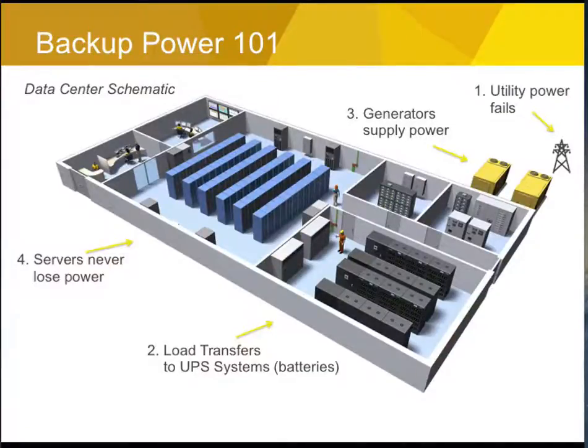Those power systems and batteries are designed to run for 5 to 10 minutes, giving time for the generators to start up and handle the load. So ideally, per point 4, the servers never lose power as long as your UPS systems work and your generators start.